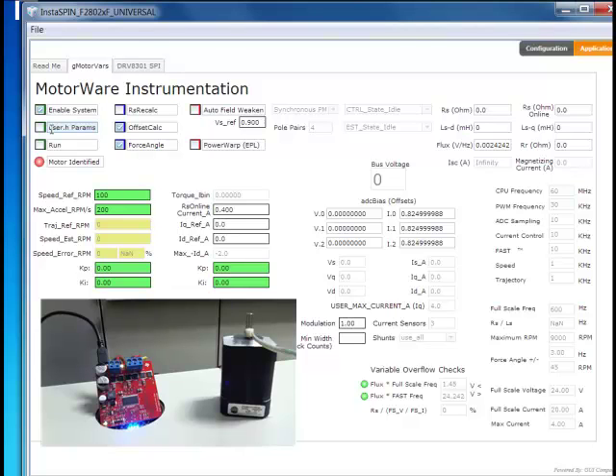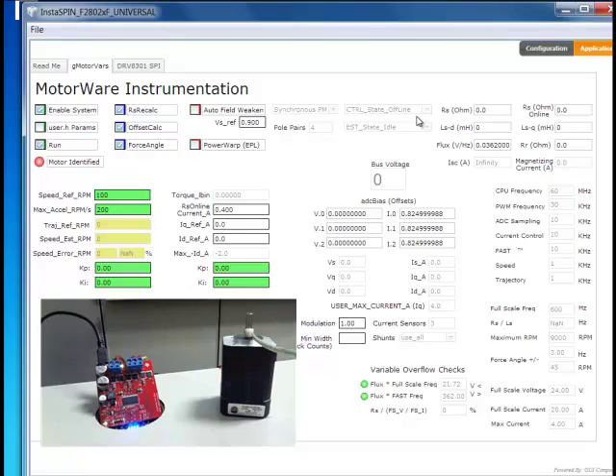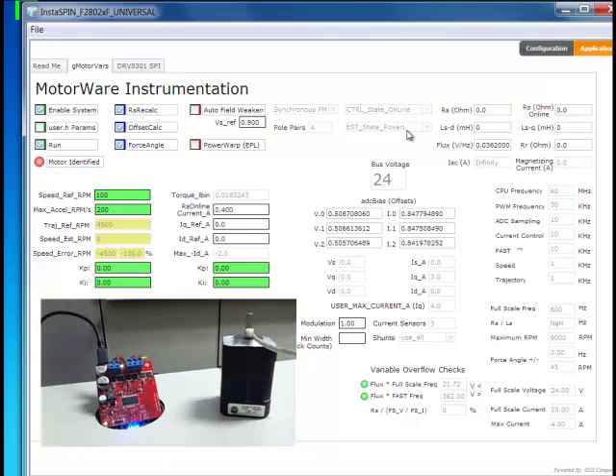And right now I don't have those for this motor necessarily. So when doing a motor ID, you deselect user.h. You can keep these default settings for the recalculations on, although during the identification process it does these anyways. By selecting run, it will start the identification phase. You can see that we can follow along here. I've moved into the online phase of R over L. Before it did that, it actually calculated the offsets.